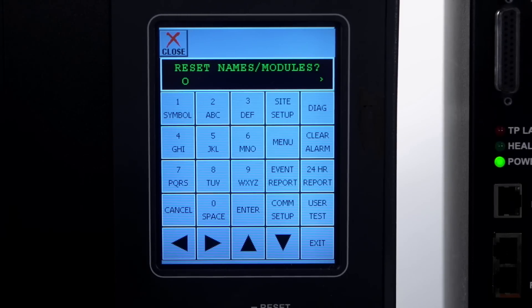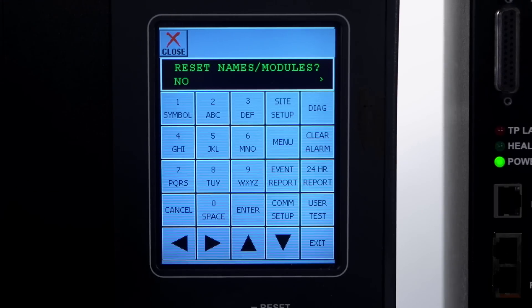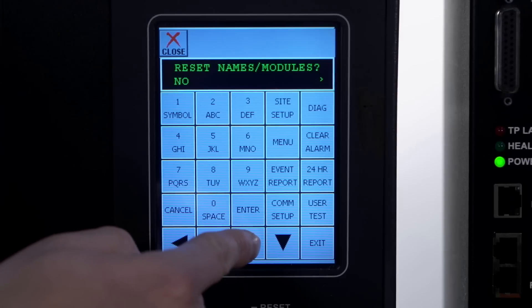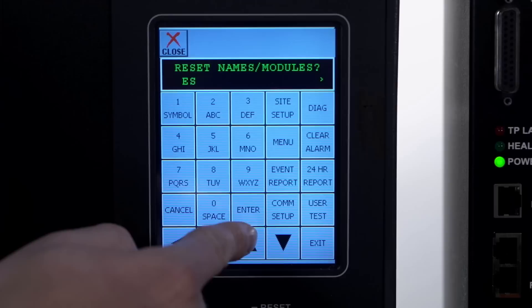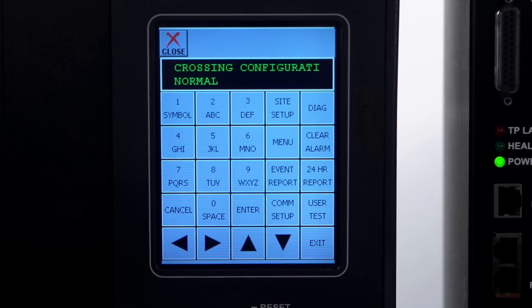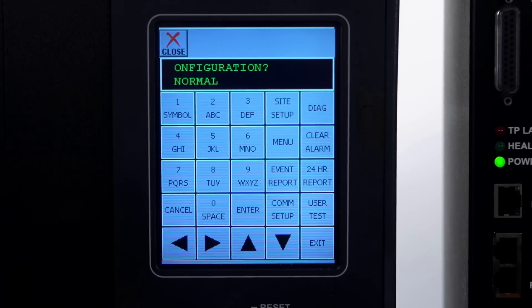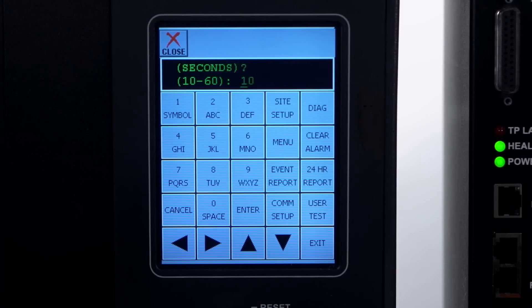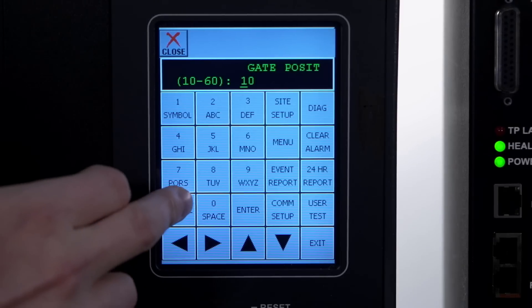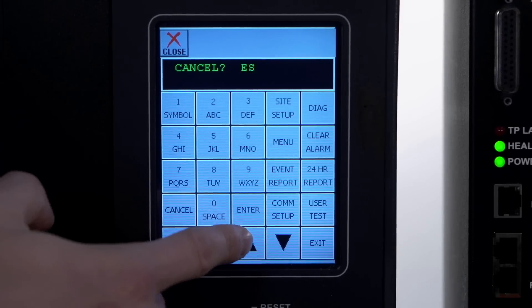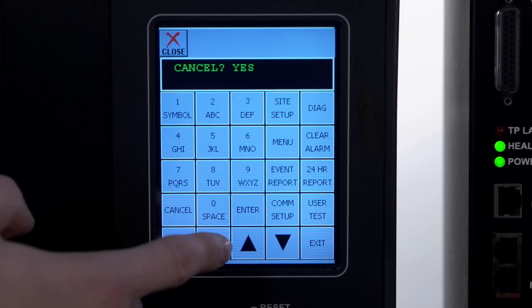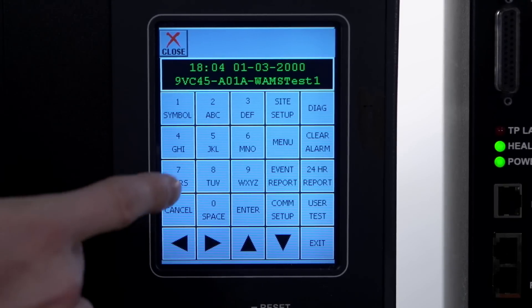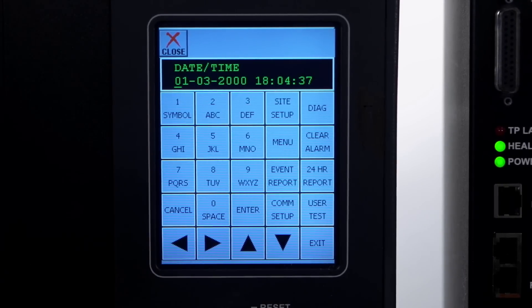If you are going to be updating any modules, such as an ILOD or a VHF communicator, as part of this process, you'll want to say yes to this question by hitting the up arrow and then pressing Enter. Note that after doing that, you will want to install or reinstall modules during the final phase of site setup. If at any point during the site setup process you do make a mistake, the best way to start over is to hit the cancel key, the up arrow to select yes, and then enter. Then start over by hitting the site setup key.